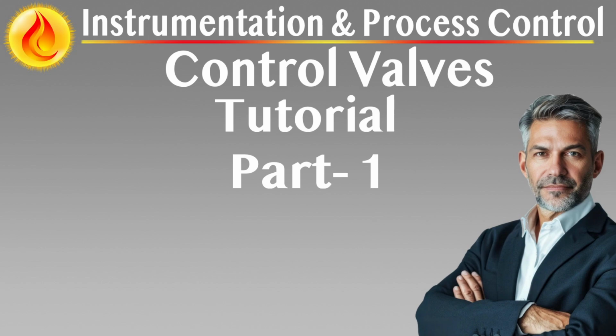Where shutoff Class 5 or V per IEC 60534-4 is mandatory, a dedicated tight shutoff valve, such as a high-performance butterfly or ball valve, must be installed in series with the throttling control valve. Metal-seated rotary valves may maintain Class 5 shutoff and throttling services, but should be used only where the control valve does not serve an IPF, instrumented protective function. Depressuring applications must not use valves in series. Control valve sizing and noise prediction considerations are detailed in the dedicated sizing appendix.